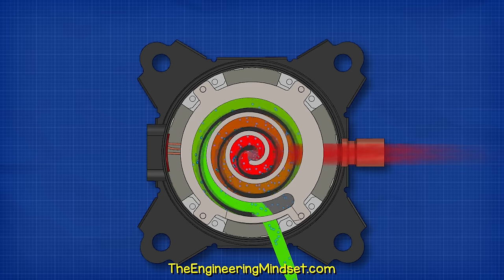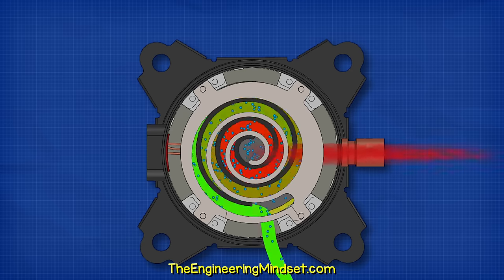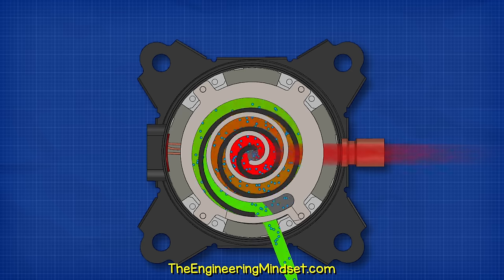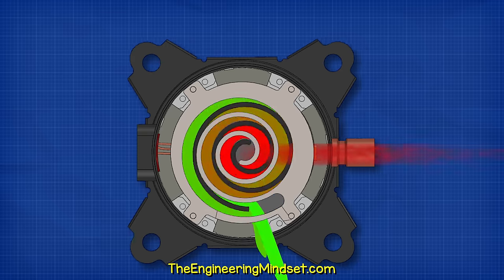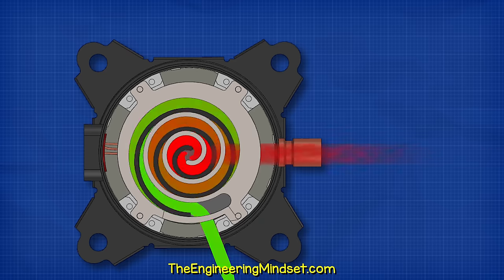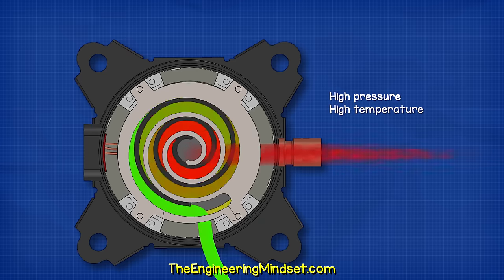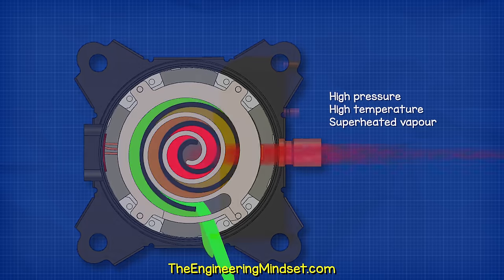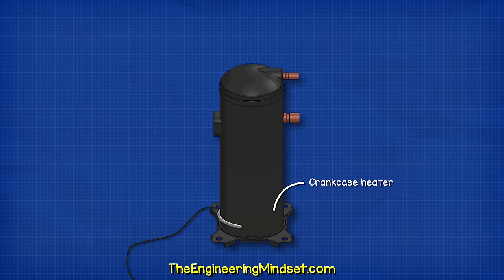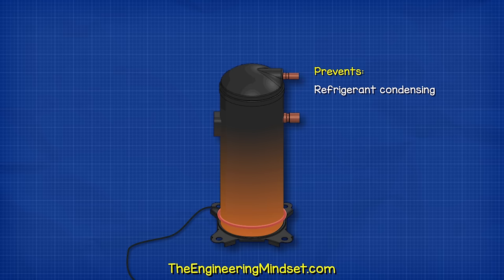Scroll compressors can handle small amounts of liquid. It can pass through without damaging the scroll plates. The refrigerant exits the compression chamber as a high pressure, high temperature, superheated vapor and flows to the condenser. A crankcase heater is sometimes fitted. This keeps the shell warm in cold climates and prevents the refrigerant condensing inside. This prevents backflow and also stops the lubricating oil from diluting.